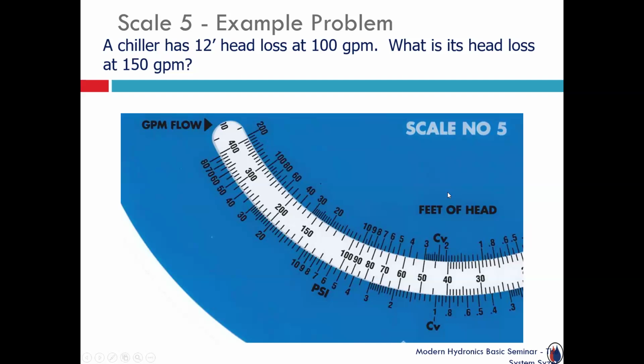And what you're going to do is say, hey, what's the known? What two pieces of information are accurate? Well, one is the flow rate. That's in the white band on scale 5. GPM, it's listed right here on either side. And then the pressure drop. So in this case, on the top side of that scale, it's listed in feet of head. You'll notice on the bottom, we reference it in PSI, pounds per square inch. But in this example, where the chiller manufacturer says I've got 12 feet of head loss, just line those two numbers up, 100 opposite 12 feet.